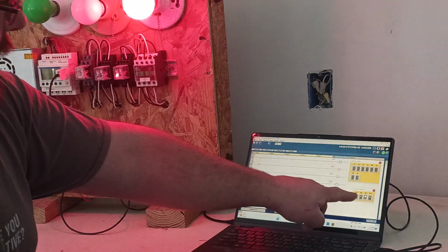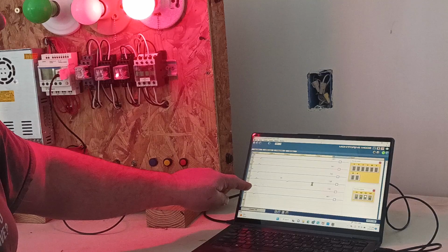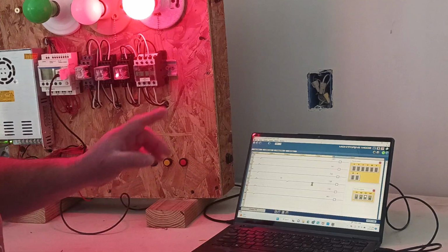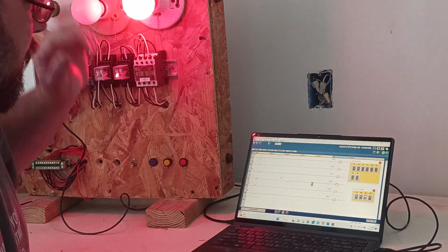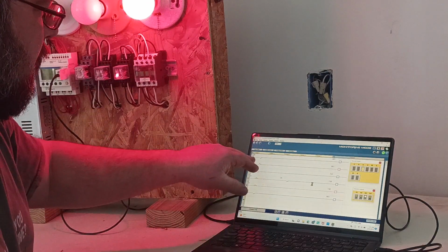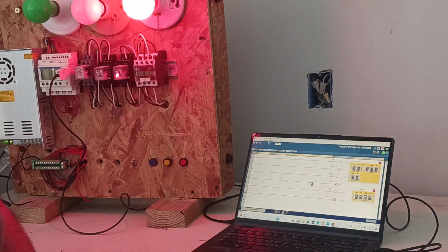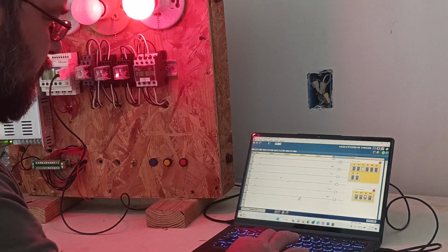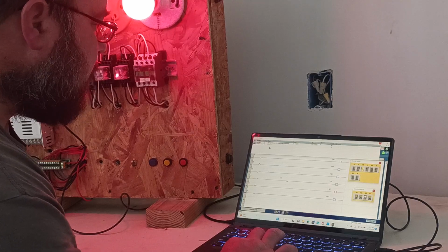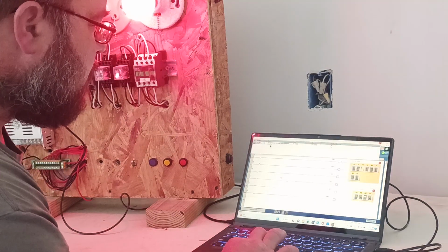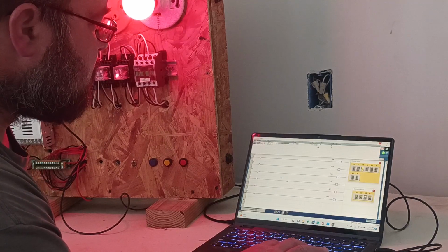As you can see, my output 3 is on. My output 3 is the red light. The reason why it's on is because my comparator is set to 0. But once I show you the output, oh, one second, I need to change that to where now I'm increasing. Okay, so now once I trip the photo sensor, we will get the first count. Let's open this window. So as you can see, here's my comparator. This is that C1 is greater than 0, which is that one. But here's my counter. It's preset to 6, so there's 6.